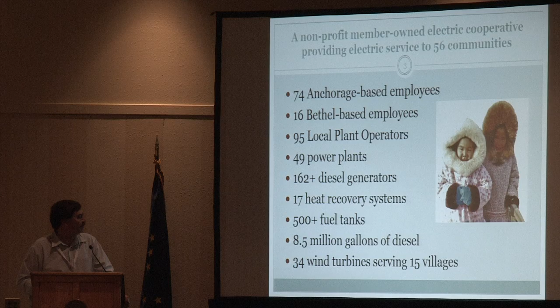I work for Alaska Village Electric. We have power plants all around western Alaska, small diesel power plants. 74 Anchorage-based employees. We acquired Bethel earlier this year, 16 employees based there, 95 local plant operators, 49 power plants out in rural Alaska, and 162 diesel generators. Currently have 17 heat recovery systems, not all of them in service right now. All kinds of fuel tanks. We buy about 8.5 million gallons of diesel a year, and we have 34 wind turbines serving 15 of our villages.